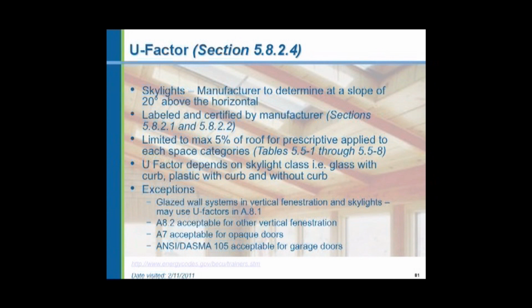Skylights can be in a sloping roof. The skylight U value has to be rated by the manufacturer for a sloping roof or a horizontal roof. And they say rate it for a roof of 20 degrees above the horizontal. And the reason is the U value of a skylight will change depending on the slope of the roof because of thermal convection currents on the inside and on the outside of the skylight.